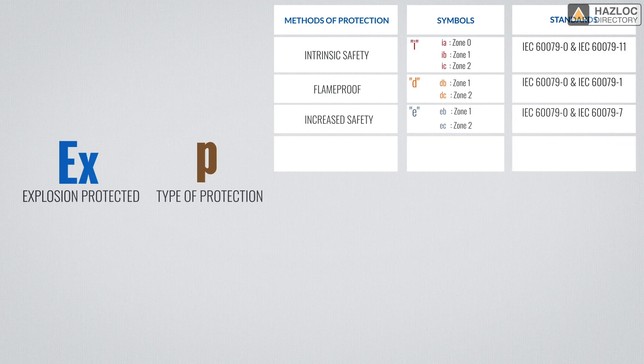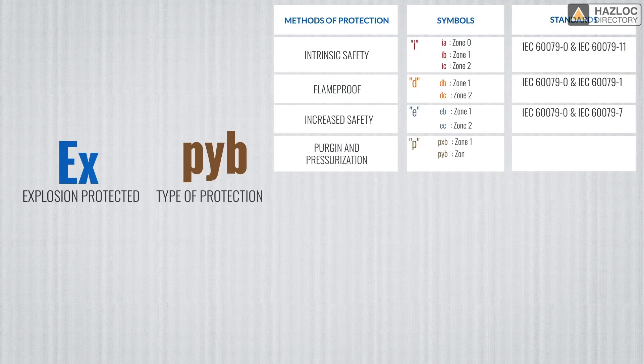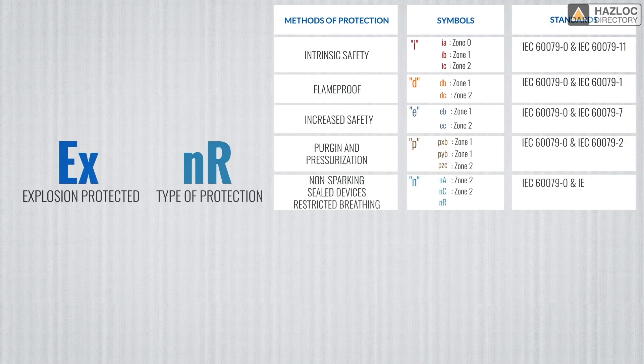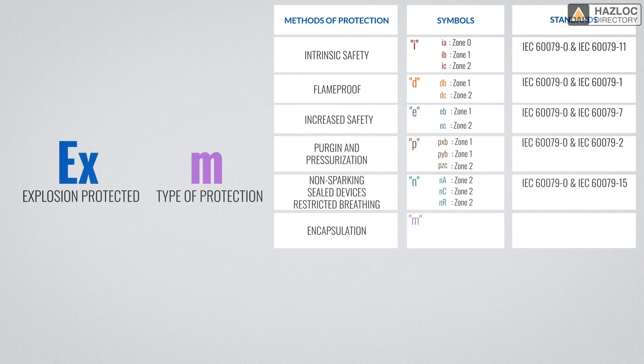Another protection technique is represented by the letter P, which means purging and pressurization. There are 3 variations on this marking: PXB for zone 1, PYB again for zone 1, and PZC for zone 2. Purged equipment cannot be assessed for zone 0. N generally means non-sparking. NA is known as non-sparking, NC is known as sealing, and NR refers to a restricted breathing enclosure. M means that encapsulation is used as the protection technique. There are MA for zone 0, MB for zone 1, and MC for zone 2.